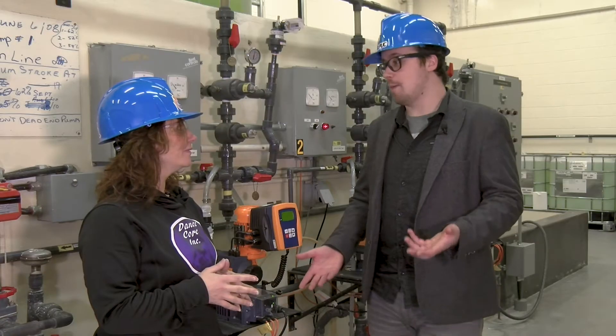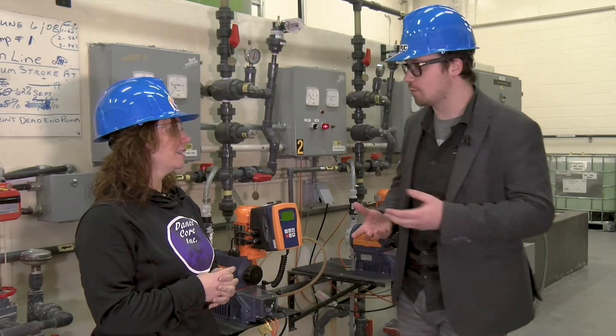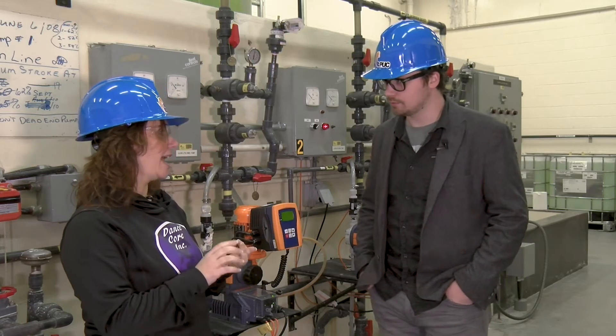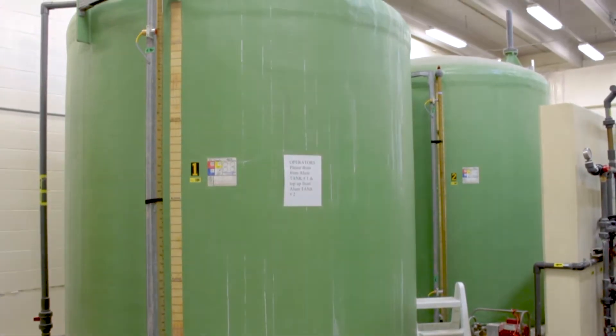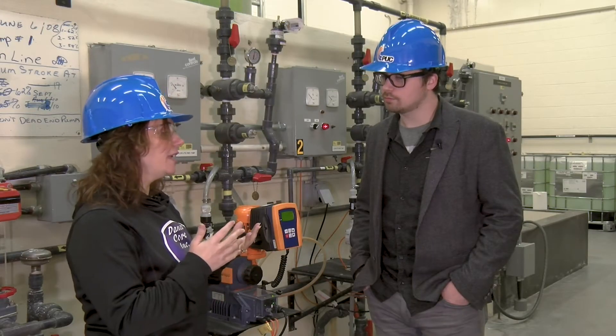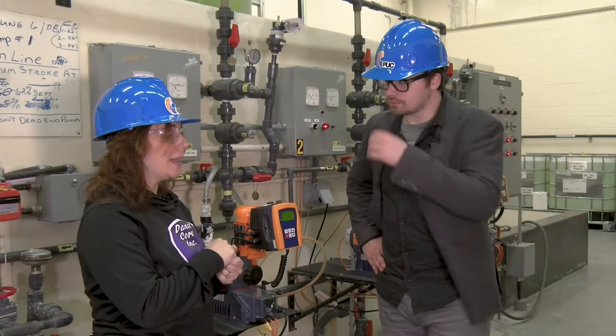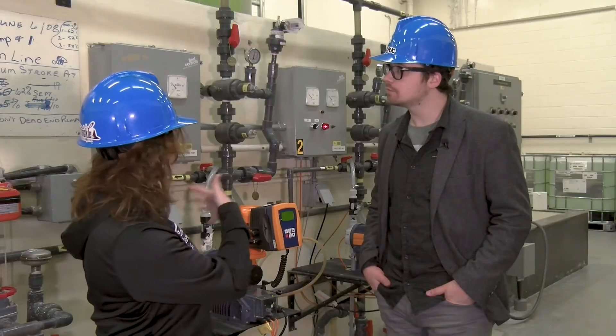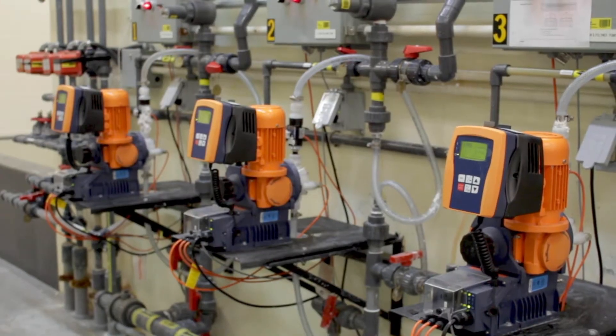I'm here with Sandra in the aptly named chemical room. When it comes to water treatment, this is the part of the process that everybody has the most concern with. We use four chemicals at the water plant: aluminum sulfate, chlorine gas, phosphates, and soda ash. Aluminum sulfate is the coagulant — it puts together the floc so the filters have something to grab onto. It's one of the ministry-mandated chemicals we can use. These are all the pumps that ensure the aluminum sulfate goes into the right area.